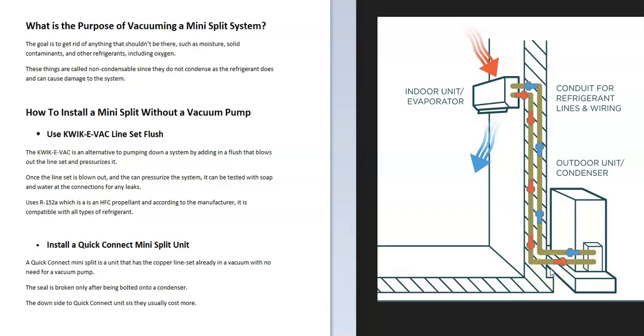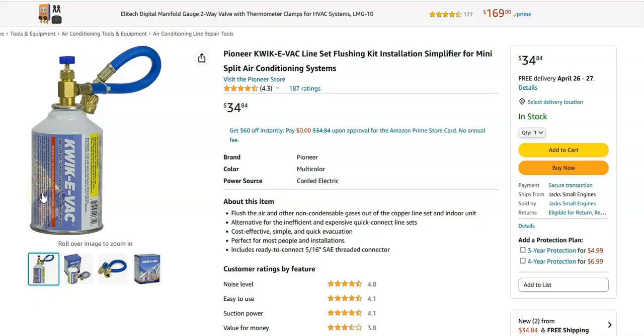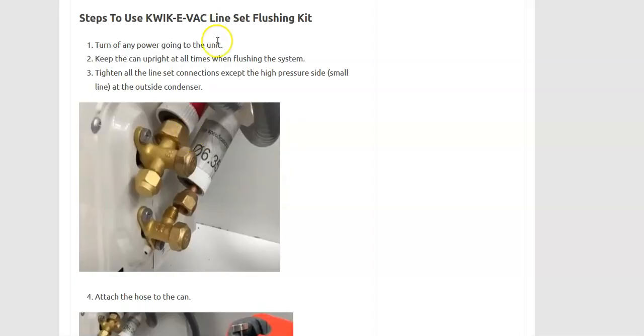What are some options if you don't want to use a vacuum pump? First, there's a thing called a KWIK-E-VAC line set flushing kit, which is from Pioneer, who manufactures mini splits. Many people use this method. To use this line set flushing kit, you tighten down all your line set connections except for one connection on the high pressure side.